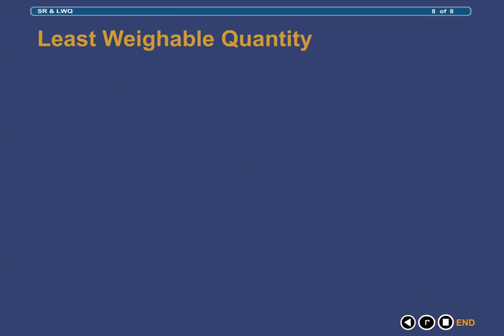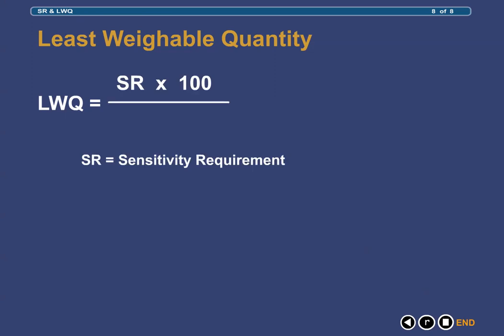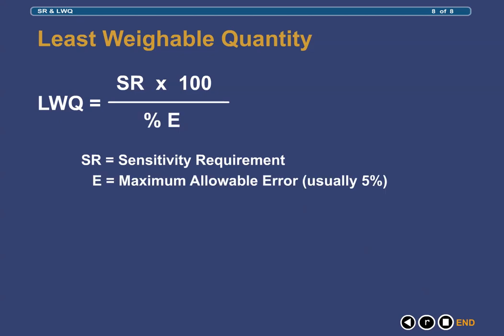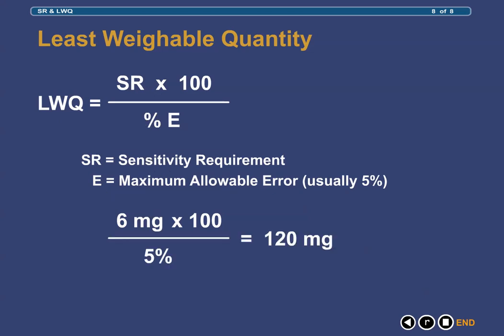Once you have performed the sensitivity requirement testing and you know the sensitivity requirement of your balance, you can then calculate the least weighable quantity using the equation where sR is the sensitivity requirement of the balance and %E is the maximum percent error allowed in weighing, typically accepted to be 5%. Applying this equation using the sensitivity requirement of 6 mg and a maximum error of 5%, the least weighable quantity calculates to be 120 mg. In other words, the minimum amount of product that can be weighed out on a Class III torsion balance with a sensitivity requirement of 6 mg and not exceed a 5% margin of error in weighing is 120 mg.